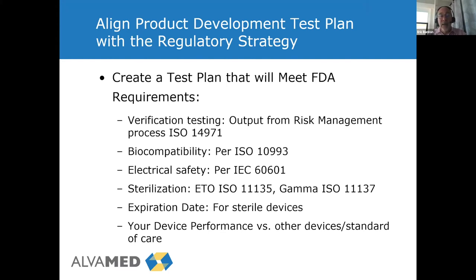They want to know how you're sterilizing, what your sterility assurance level is, expiration date for sterile devices, your shelf life, how you test that. And then for pre-market notification, perform your device performance versus other devices or standard of care. These are examples, but think about this in your product development process, not at the end. You could see how at the end of the process, when you go through this regulatory strategy, you say, oh boy, I didn't realize I needed to do this type of testing, or test to the standard, and I didn't do that. You don't want to do that at the end of the process. You want to make sure you understand that up front.